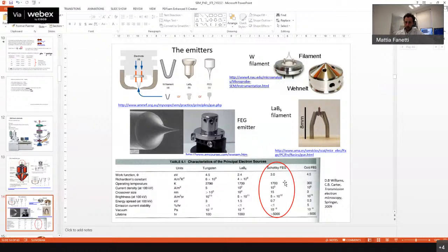Because the beam which is coming out of the filament and out of the anode assembly is monochromatic as much as possible, and also coherent and spatially confined. Okay, so if you have molecules of atmosphere around which can scatter with the electrons, you will spoil the characteristic of your beam, and so decrease the resolution a lot.